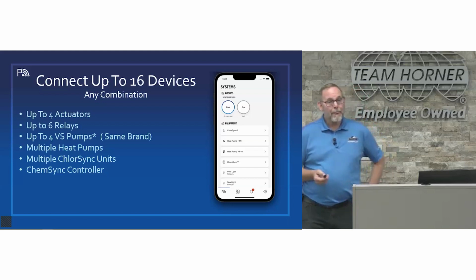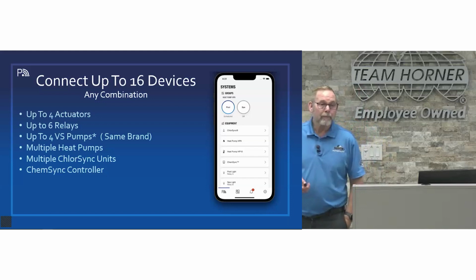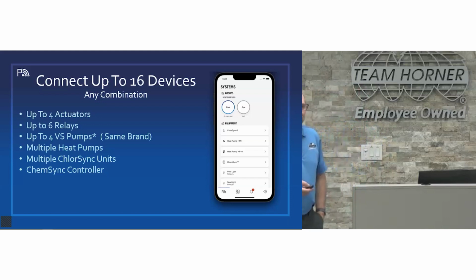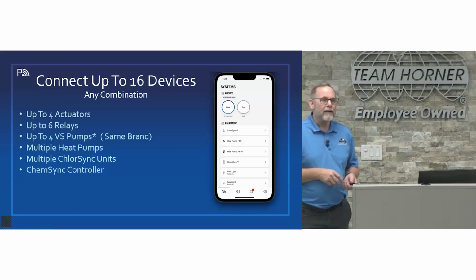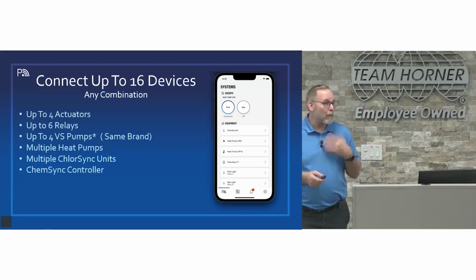Heat pumps don't have to be the same body to daisy chain them. When daisy chaining, we connect the heat pumps together using just a low voltage communication wire and designate one as the lead. That lead brings on all the other follower units, so they function as one heat pump, and you only have to set the temperature or make adjustments on the lead unit.